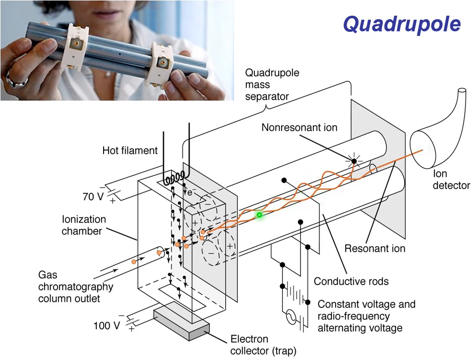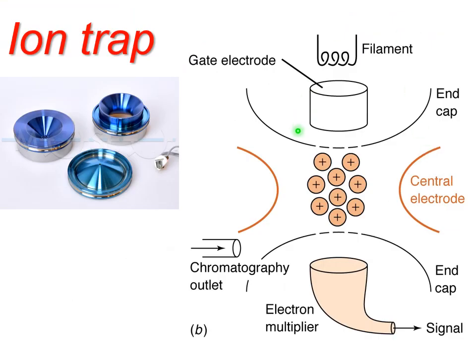So we scan masses, for example, from 50 to 500 mass numbers, and in less than one second we have a mass spectrum with resolution of around one-half of atomic unit, maybe slightly better. This is a relatively inexpensive design. A similar design is the ion trap. Again, you can see it's reasonably small.